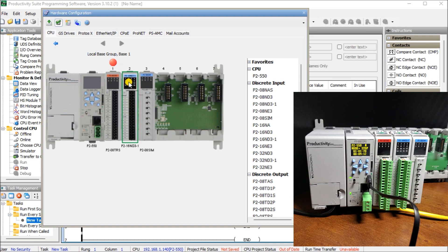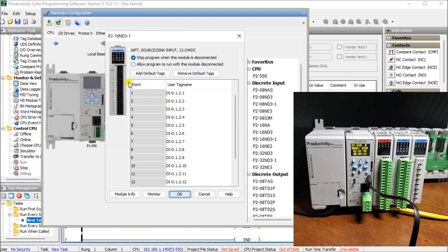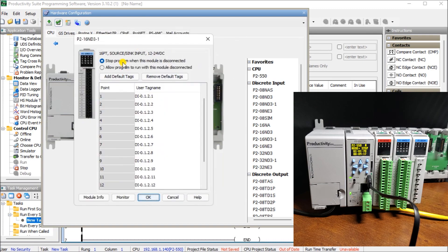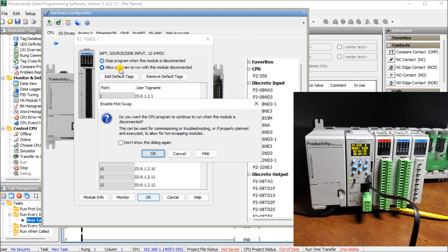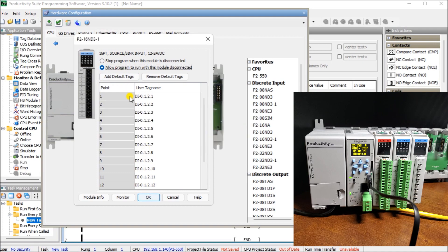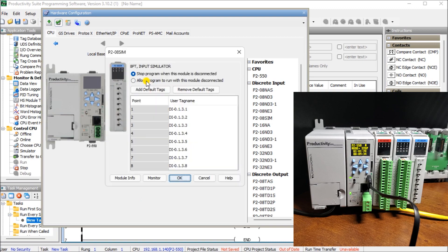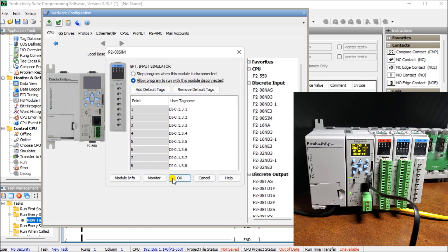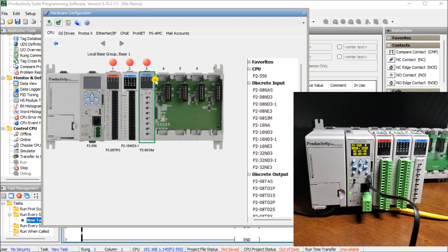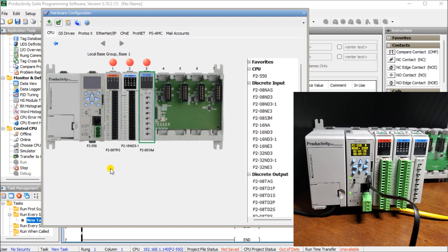Now let's do the same thing for the next two input cards. So there's my input card, 16, 16 point source sink input, 12 to 24 volt. And there's my default inputs, my default tags. And then what we'll do is we'll enable our hot swap. Okay. And then for our simulator, again, here's my input points. My input points will allow the hot swap. So here is my end rack. So the productivity 2000 automatically will configure. It will read the hardware, bring it back, and then we can enable our hot swap options. So let's close that down. So now we have configured that information.